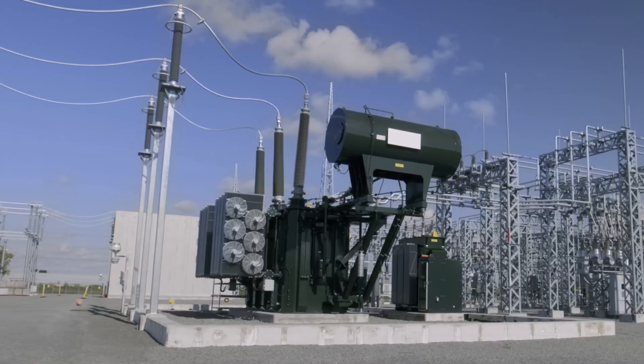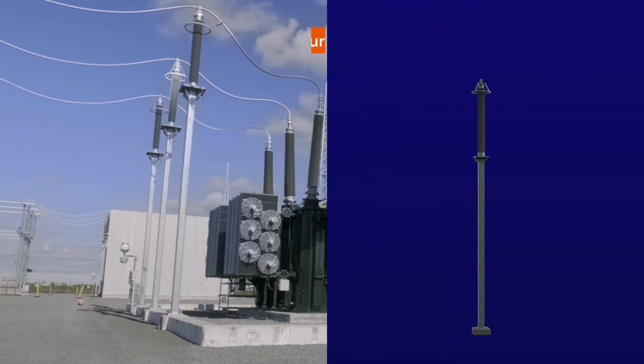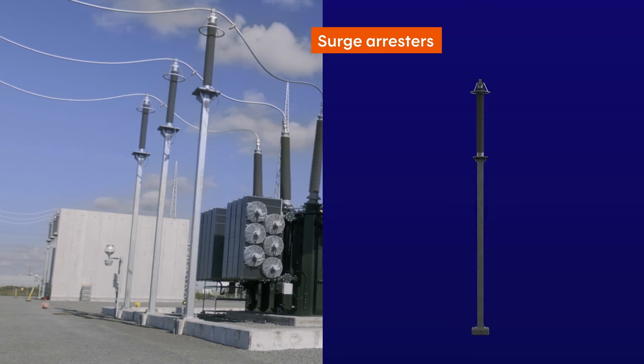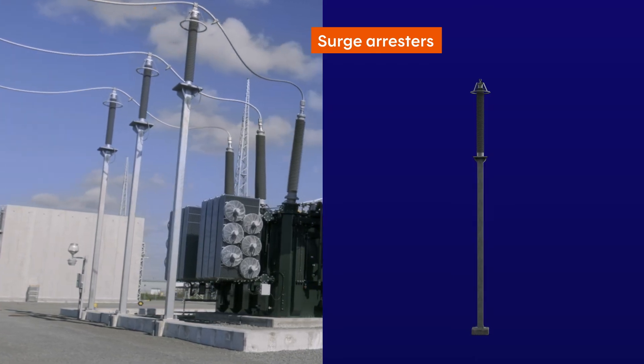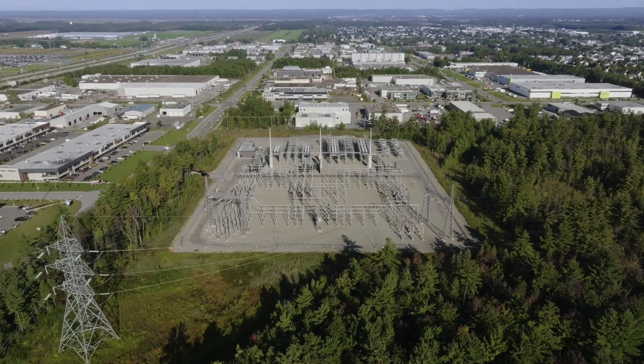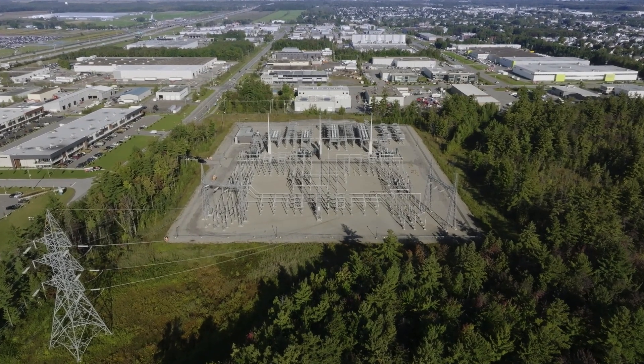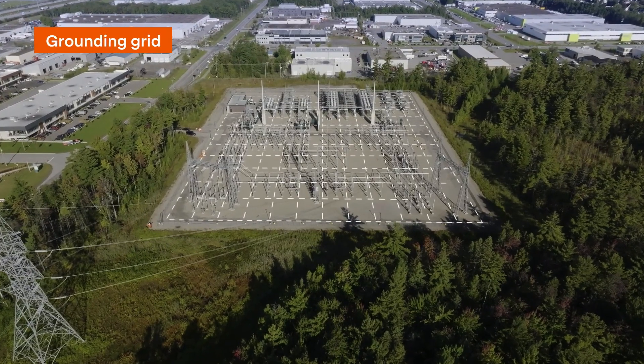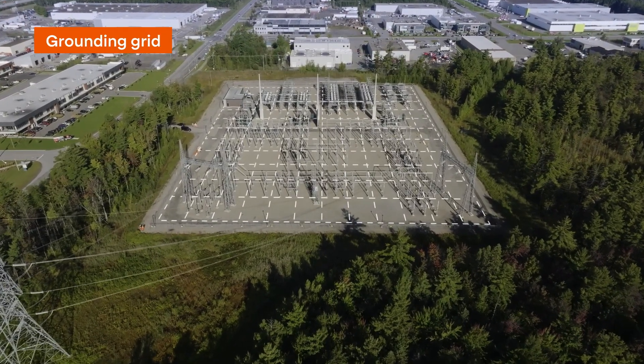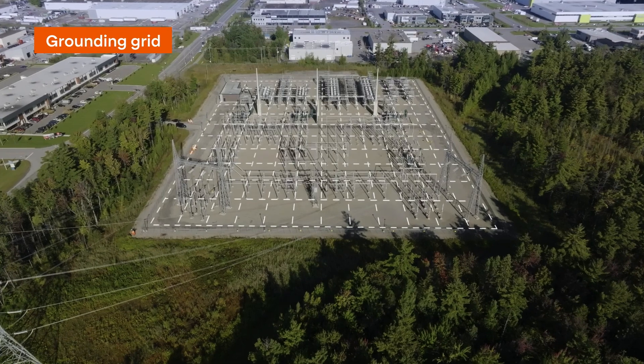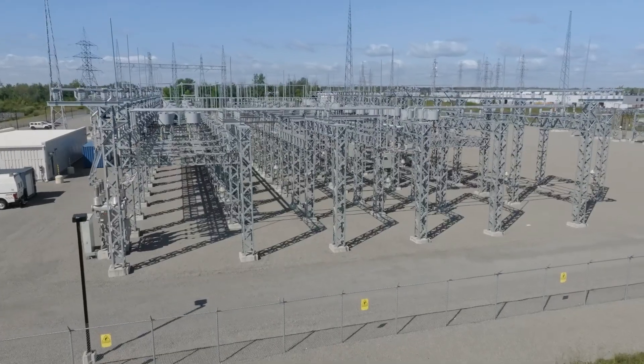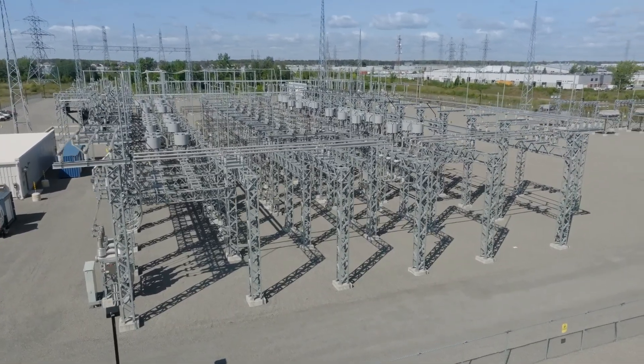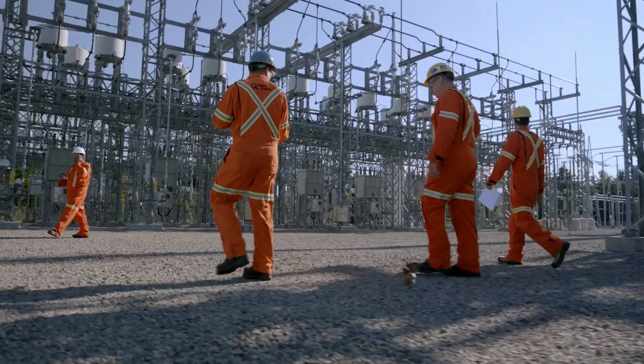Not far from the transformer are the surge arresters. They protect the transformers from overvoltage. When there are lightning strikes or switching operations, they send the electricity towards the ground. And on the ground, there's a grid of metal wires — a safety device that protects the entire substation. This grounding grid disperses the electricity downwards as a safety measure. As it leaves the transformer, the electricity is guided to more bus bars, breakers and disconnect switches before moving to its next destination.